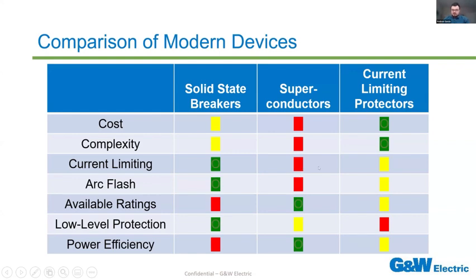In terms of available ratings, superconductors could be said to be the best just because you can apply conductors to just about any system. Current limiting protectors would come in second because they can go up to extremely high ratings, say up to 38 kV, up to 5,000 amps, 120 kA short circuit rating. While solid state breakers are unfortunately at this moment very limited in the kind of ratings they can go to, and once again increase in size and expense pretty dramatically as the ratings increase. However, that's expected to improve as the years go on.